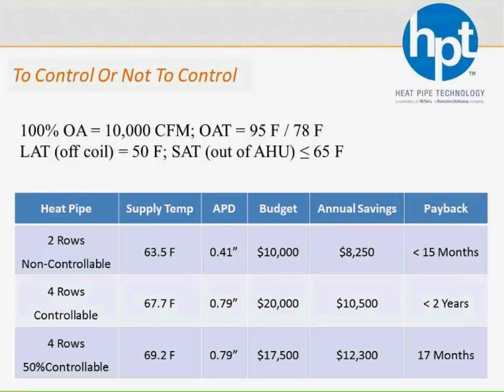So when you get into our selection software, it's easy to pick a non-controllable heat pipe, it's easy to pick a controllable heat pipe, but you do not have the option for a partially controllable heat pipe. That is something we have to do internally. So if you have a job where you know you want control valves, but you know that you'll want some reheat all the time, let us know and we'll work with you to get the right selection to optimize not just your savings up front, but down the road as well.